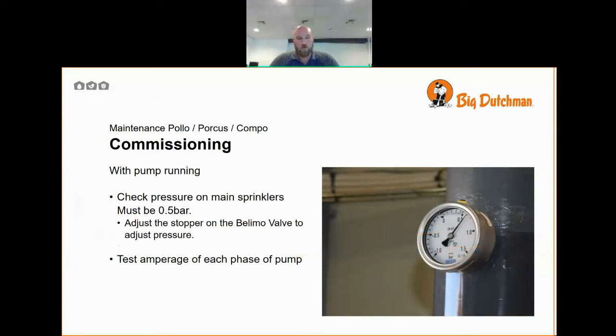Once we have the system running at our 0.5 bar, we'll test the amperage on each phase of the pump and check that the pump is running on the pump curve. With checking the pressure, please bear in mind that from the pressure gauge to the height of the sprinklers, you will need to add an additional 0.1 bar per meter of head that you go up.